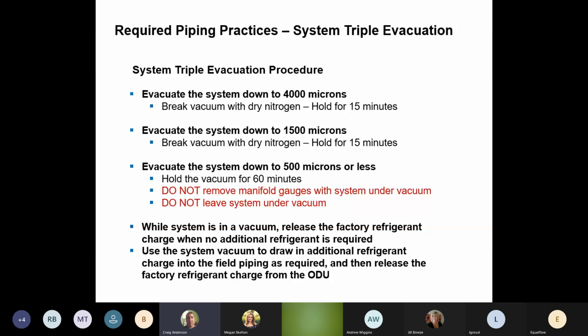So when you turn that vacuum pump off, chances are if it's a new system, you're going to be reading about 78 microns because it's going to pull it down to that. And then once you turn it off, that micron gauge is going to climb. We're looking at that micron gauge and we need to make sure that it stops and doesn't go over the 500. If it goes over the 500, then chances are we still have moisture in the line or we have a leak in the line. You want to keep it under 500 and it needs to hold under 500.